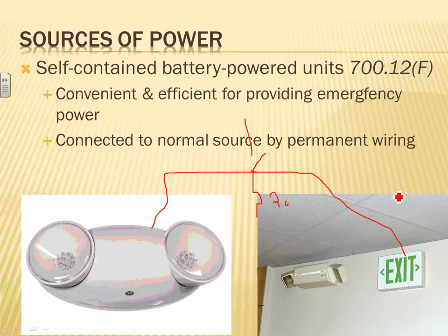So that's the most important thing about these. They are powered, no generators, they have batteries on them, that's the second source. They have a little relay that flips upon the loss, the locally or global loss of power in this room. Local as in Chad went and tampered with the circuit that feeds this light here. That light will come on, and if a storm knocks down the transmission line coming to your building, the distribution transmission line that feeds the area, it will also come on.